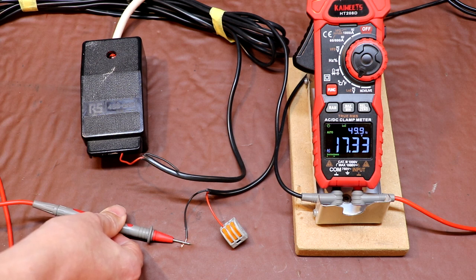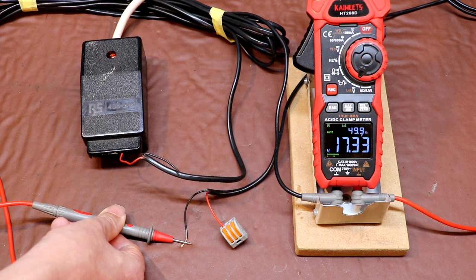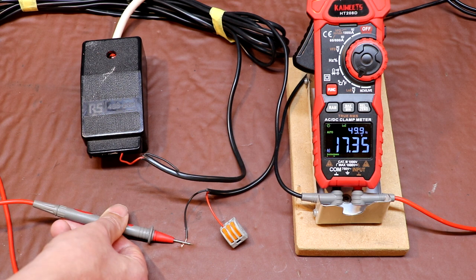So we can actually see that this much lower 30 kiloohm input impedance is pulling that voltage right down. So using this low Z function, we can have a pretty good idea that the voltage that we're seeing here is a ghost or a phantom voltage, and it wasn't a true indication regarding the energization of the circuit.